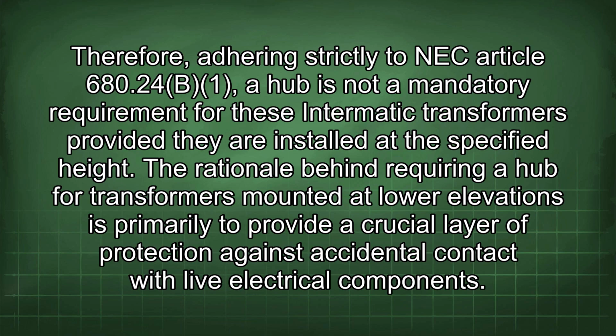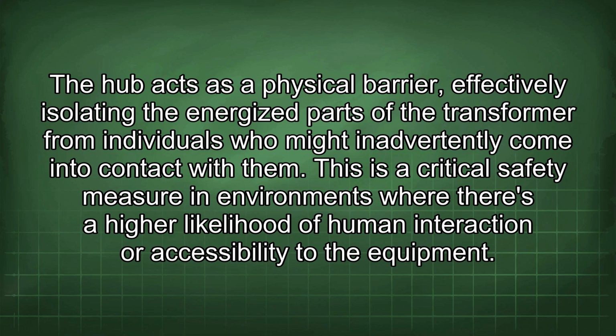The rationale behind requiring a hub for transformers mounted at lower elevations is primarily to provide a crucial layer of protection against accidental contact with live electrical components. The hub acts as a physical barrier, effectively isolating the energized parts of the transformer from individuals who might inadvertently come into contact with them.